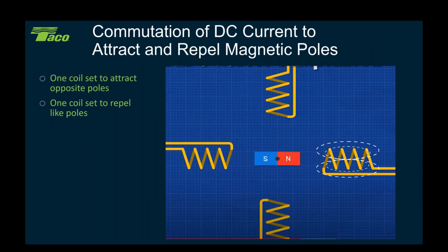Okay. So what we end up with is we have one coil attracts the opposite poles and one coil repels the like poles. And that's what causes the rotation inside the motor. It works on the basic principle of magnetism that opposites attract and likes repel. It's that simple. There is nothing magic going on. There's nothing oddball. And all motors, by the way, all motors work by the exact same principle of magnetism. Okay, it's just how we create that magnetic field. That's the big difference: how we create the magnetic field in the rotor and how we create it in the stator.